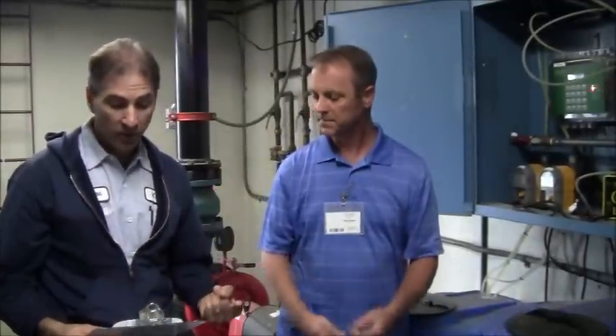Okay, that's perfect. So we went into why we treat water, different types of loops, and the overall water treatment process, which you got a gist of with the controller and the different types of chemicals. We do water treatment testing here every single day, and we're not going to go into the process of how to test the water, because depending upon where you work, it could be a different chemical, which could require a different testing procedure, because every place could be unique. That's correct. But your water treatment professional will provide you with a water treatment book and the testing process, and what to do when you see low or high readings.